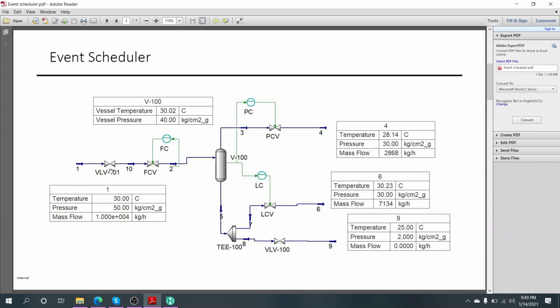Okay. Yeah, but that also depends. In some cases, if it closes very fast and we have a long line upstream that is continuously coming, then if we close this very fast, we will have what we call a water hammer. It will hit this valve and create a pressure wave. That pressure wave, depending on the design pressure of the pipe and everything around it, if it is higher than the design pressure of the pipe, then the pipe can burst.